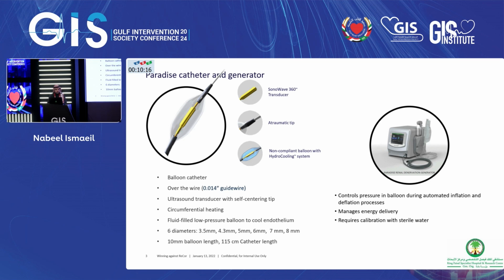If we look at the other model, which is the Paradise catheter, it's a balloon catheter that has a SonoWave 360 degrees transducer with atraumatic tip. And that transducer is covered by a non-compliant balloon. And the point of that is that because of the heat that is generated by the transducer, there is a very unique hydro-cooling system inside that balloon.